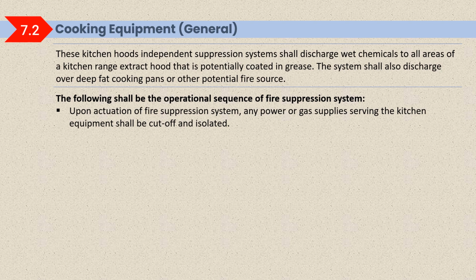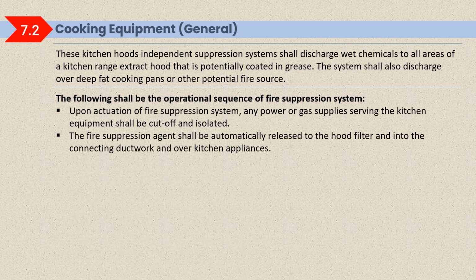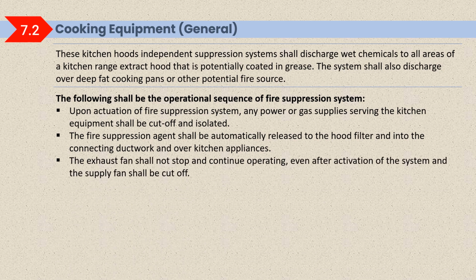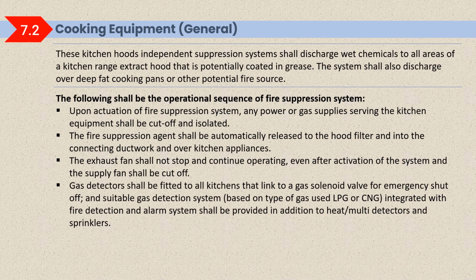Upon actuation of the fire suppression system, any power or gas supply serving the kitchen equipment shall be cut off and isolated. The fire suppression agent shall be automatically released to the hood filter and into the connecting ductwork and over kitchen appliances. The exhaust fan shall not stop and shall continue operating even after activation of the system, and the supply fan shall be cut off.